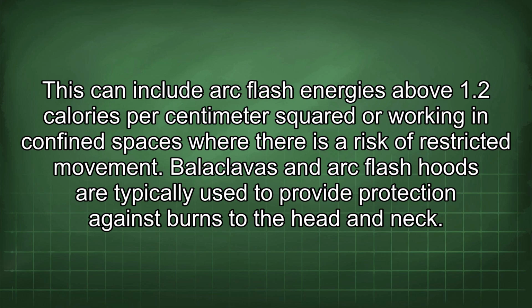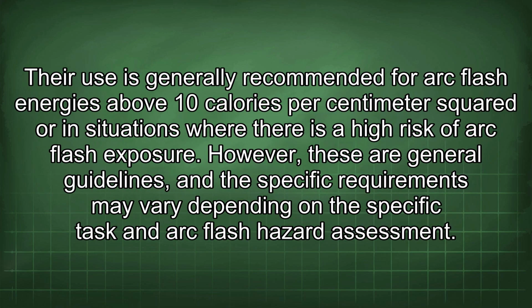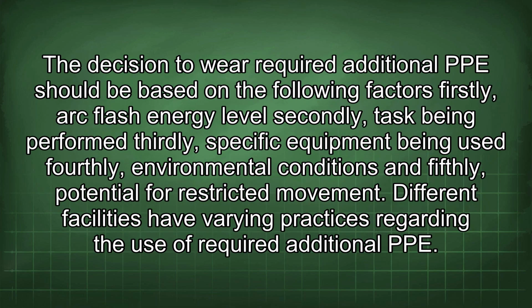Balaclavas and arc flash hoods are typically used to provide protection against burns to the head and neck. Their use is generally recommended for arc flash energies above 10 calories per centimeter squared or in situations where there is a high risk of arc flash exposure. However, these are general guidelines, and the specific requirements may vary depending on the specific task and arc flash hazard assessment. The decision to wear required additional PPE should be based on the following factors: firstly, arc flash energy level; secondly, task being performed; thirdly, specific equipment being used; fourthly, environmental conditions; and fifthly, potential for restricted movement.